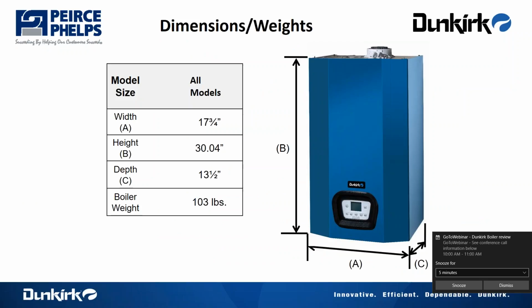Dimensional data on the boiler: 17 3/4 wide, 30 inches high, 13.5 deep, weighs 100 pounds. This diagram shows the diverter valve in action, where we're showing a comfort heat call on the left. We have hot boiler water going out into the system, returning back. On a call for hot water, the diverter valve closes, diverts all hot boiler water either into the brazed plate to divert all BTUs to generate domestic hot water, or again, in lieu of the brazed plate, we hook the boiler up to an indirect fired hot water heater. Diverter valve performs in the same fashion.